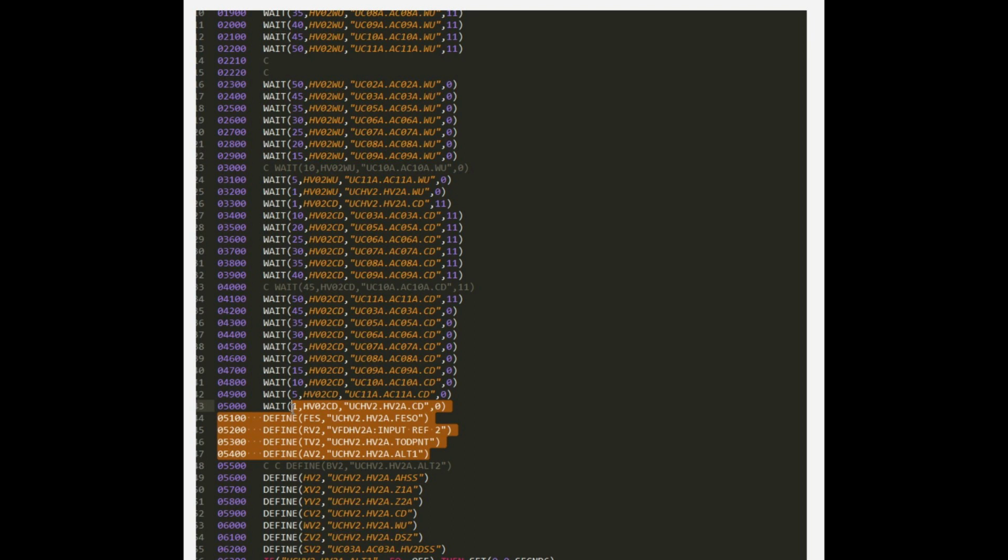When using multiple programs in an Apogee field panel, try to create programs that are roughly the same number of lines per program. Apogee field panels sequentially execute one line of each enabled PPCL program.